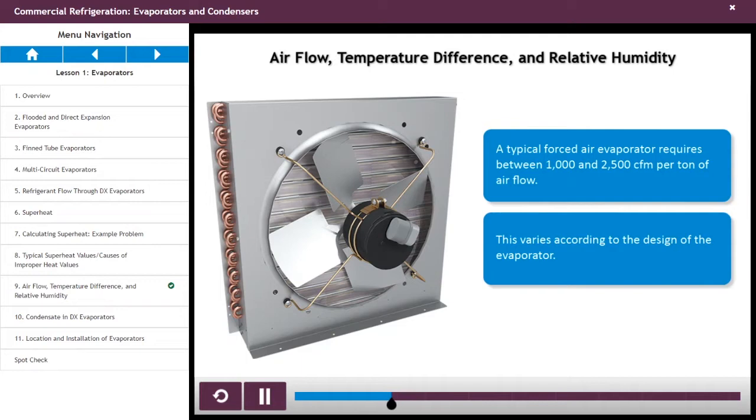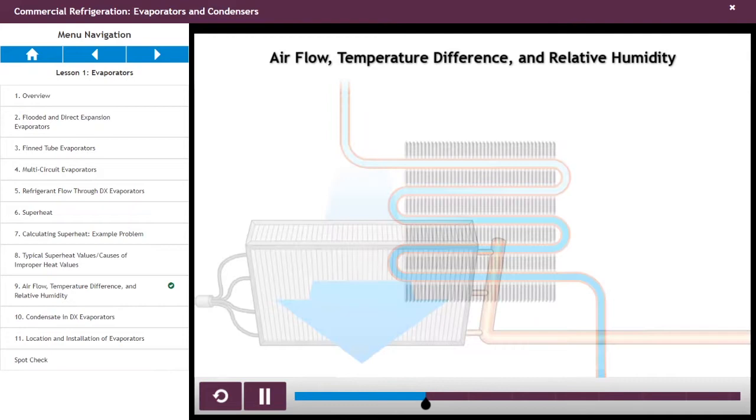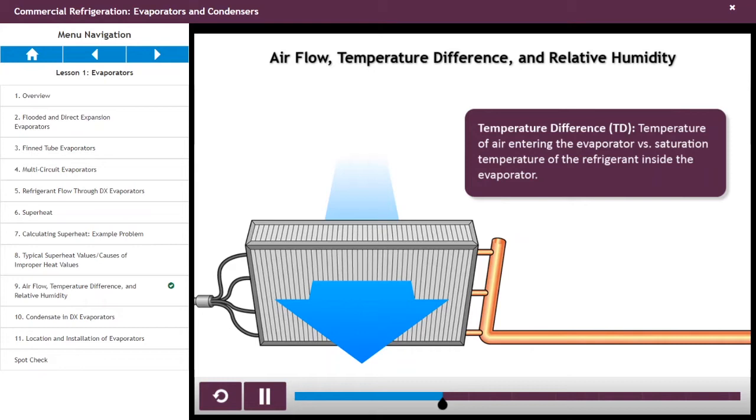Another important factor is the temperature of air entering the evaporator compared to the saturation temperature of the refrigerant inside the evaporator. This is called the temperature difference of the evaporator, also known as the TD.